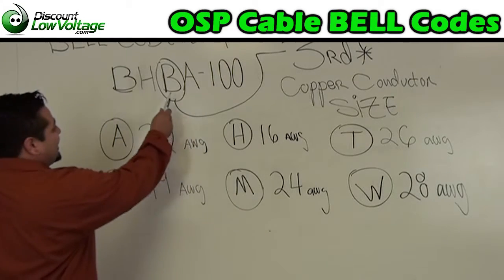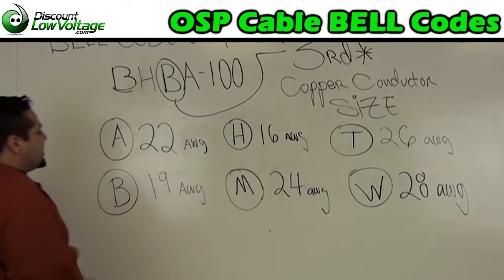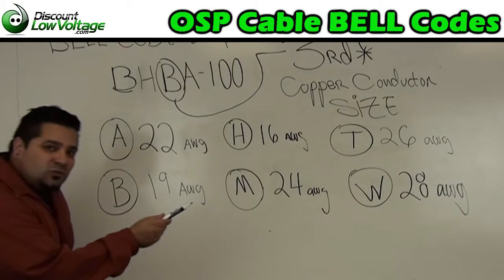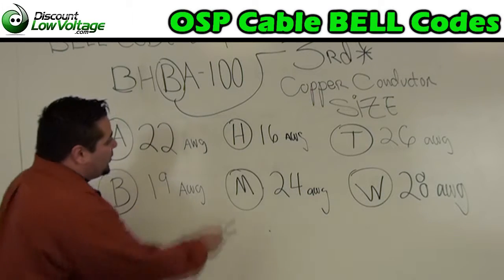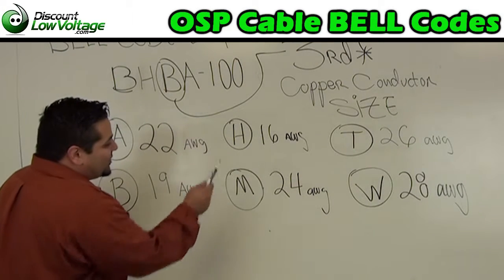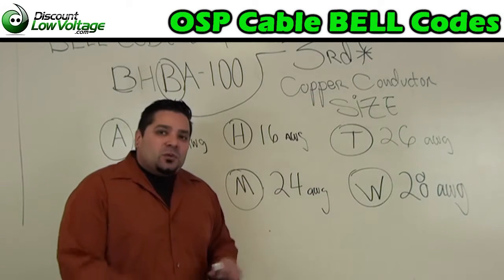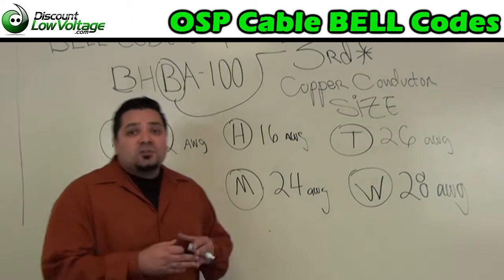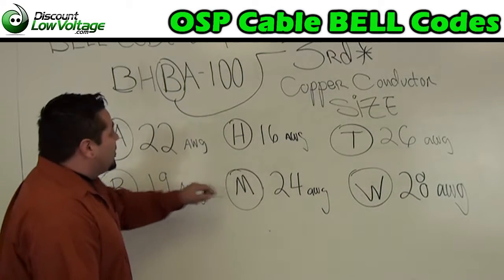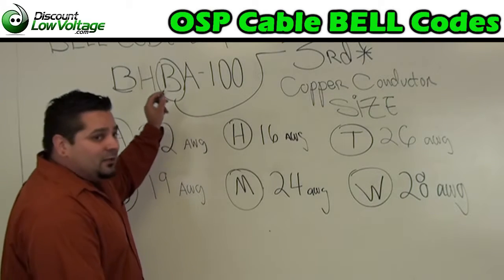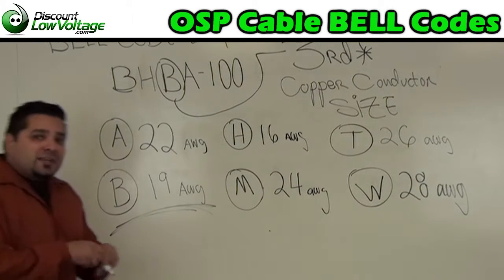The third designation stands for the copper conductor size. A is 22 gauge. B, 19 gauge. H, 16 gauge. M, 24 gauge. T, 26. W, 28. Personally, the most common size I've seen is your 24 gauge, the M. But in our code here, we have a B, which is telling us we have a 19 gauge cable.